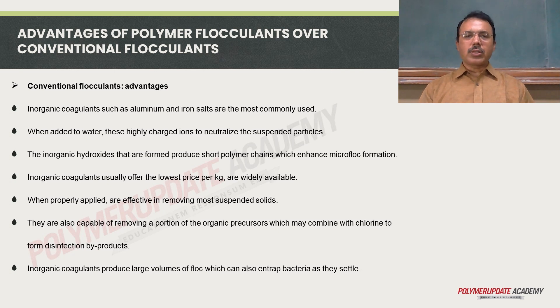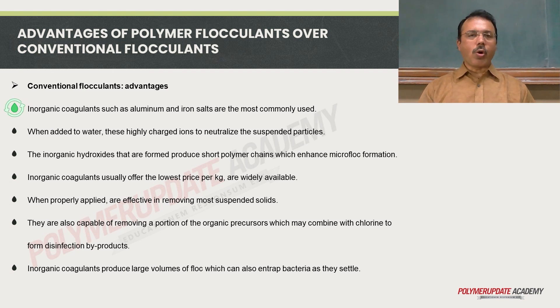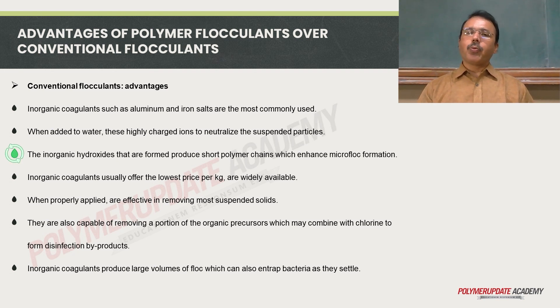Let us talk about some advantages of conventional flocculants and why they were selected for use as coagulants in industry. These substances used as coagulants are inorganic substances — salts of aluminum, iron, etc. — and they are widely used. When added to water, these highly charged ions neutralize the suspended particles. The inorganic hydroxides formed produce short polymer chains, and these chains enhance microfloc formation.